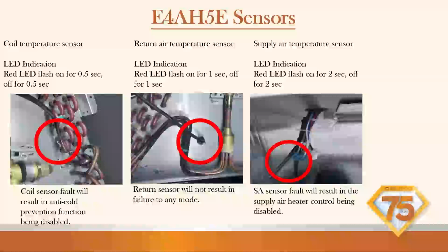Now, if you're doing a retrofit, technically there's a strainer in the outdoor unit and there's a strainer in the air handler. There's no strainer in the evaporator coil, so keep that in mind. This air handler, the E4AH5, has a strainer before the indoor TXV. So if you are using the outdoor unit with this air handler, you would not need a filter dryer. I recommend it, and I'll go into that in a little bit.